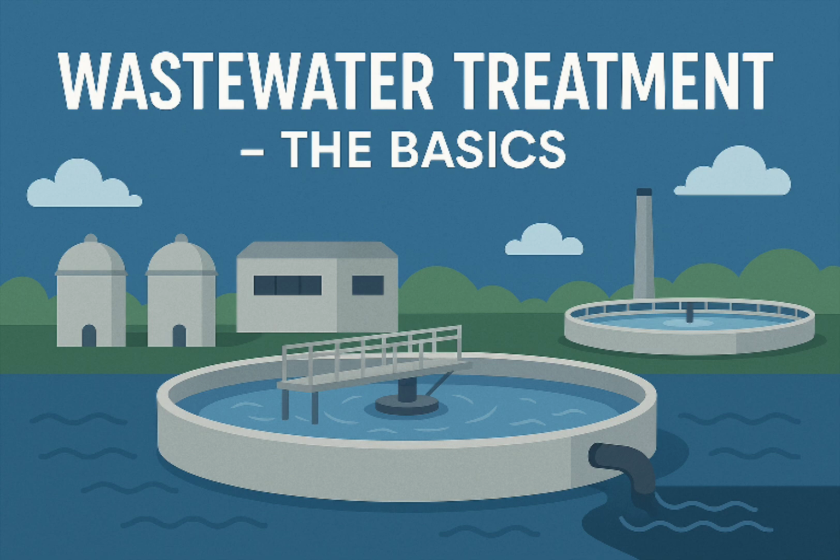I also saw a mention of separating different types of wastewater, black water and gray water. Yes, that's an area getting more attention. Separating black water, which is from toilets and has most of the pathogens and nutrients, from gray water from sinks, showers, laundry, allows for different approaches. Gray water is much easier to treat and can potentially be reused more readily for non-potable things like irrigation or toilet flushing with minimal treatment. Yeah. You also have things like composting toilets or incinerating toilets that avoid using water altogether for that waste stream.